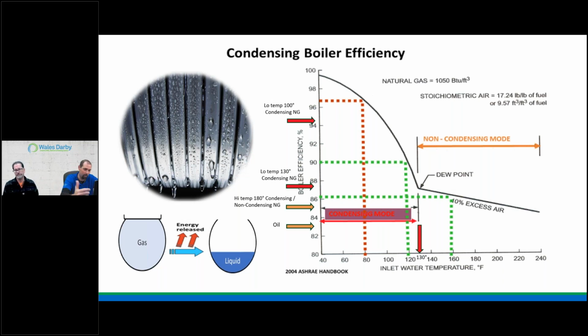Yeah. And that's 100%. We do it at Radiant, why can't we do it with anything else? Absolutely, and I have slides to bring that point up exactly. It's a very true thing that we play tricks on our minds. Like we think the emitter determines that it can only be this water temperature, and that is not the case. But yet, like Eric's point, as I've shown in slides, and you'll see it later, why is it okay here? Yeah. Really what it comes down to is surface area. Yeah. The more the surface area, the lower the water temperature, you still achieve the BTUs required.